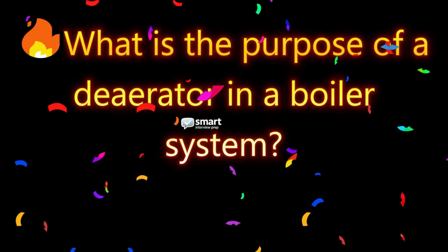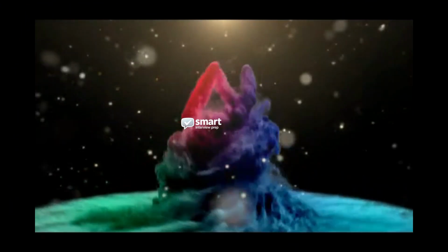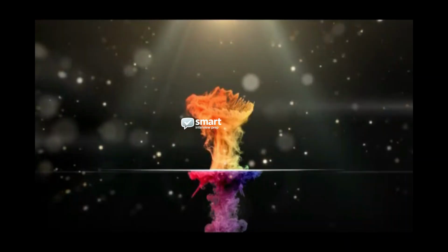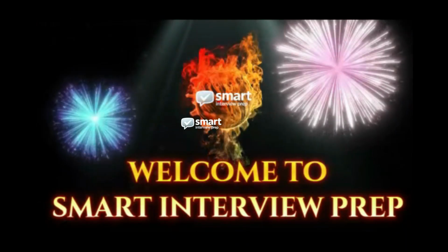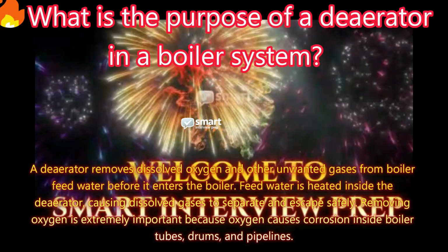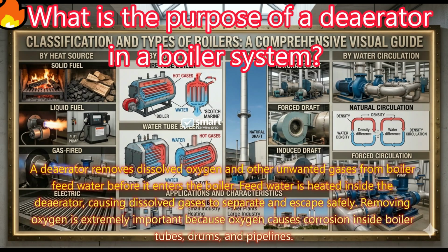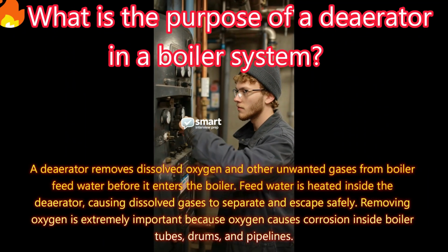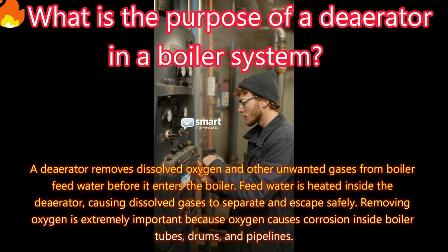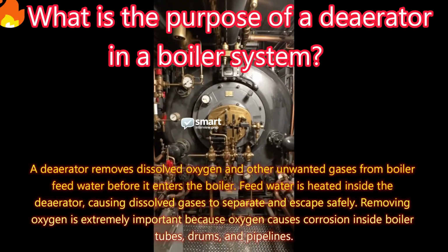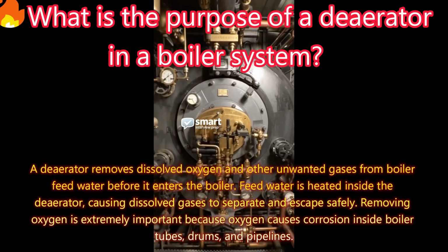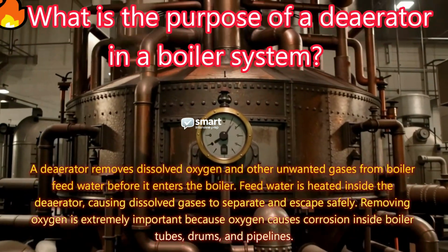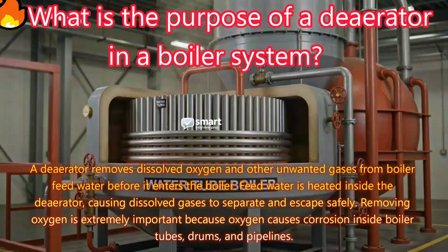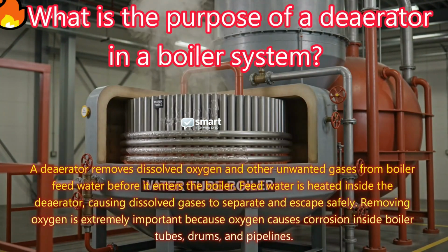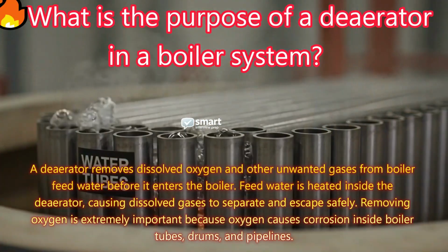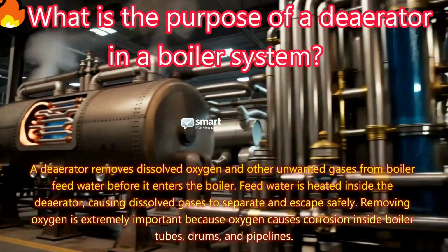What is the purpose of a deaerator in a boiler system? Answer: a deaerator removes dissolved oxygen and other unwanted gases from boiler feed water before it enters the boiler. Feed water is heated inside the deaerator, causing dissolved gases to separate and escape safely. Removing oxygen is extremely important because oxygen causes corrosion inside boiler tubes, drums, and pipelines.